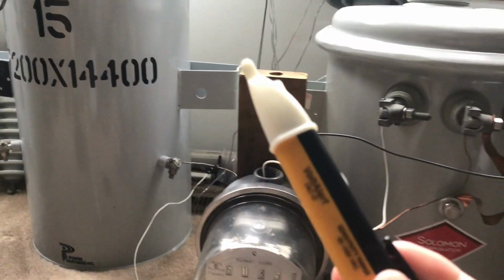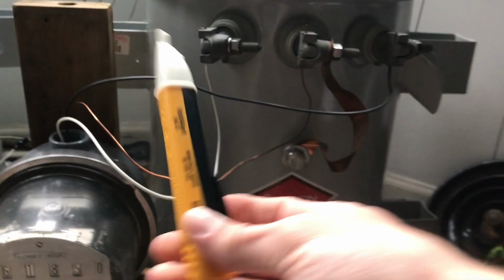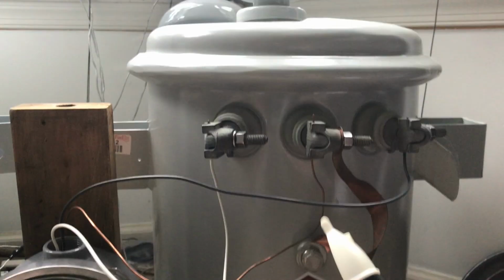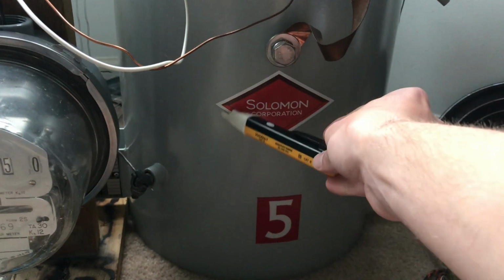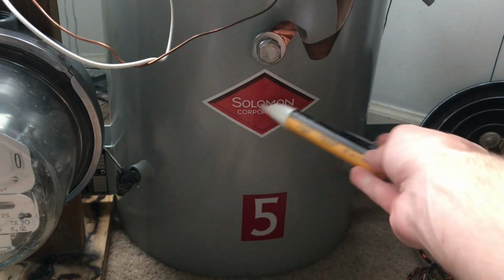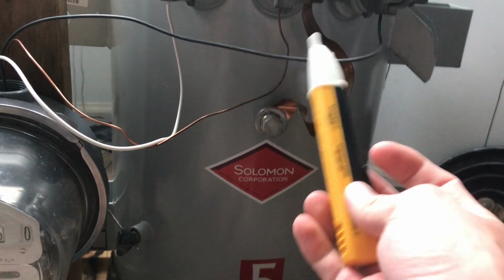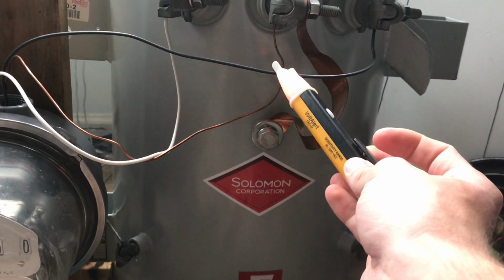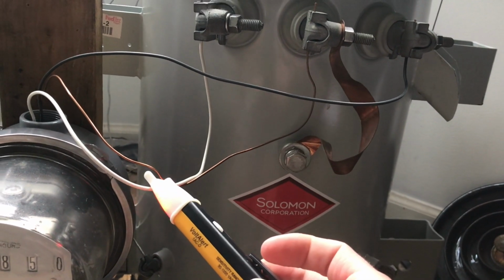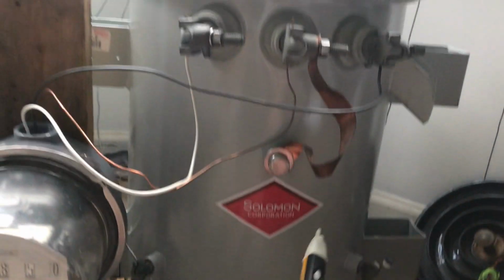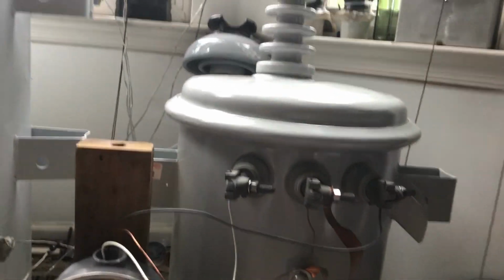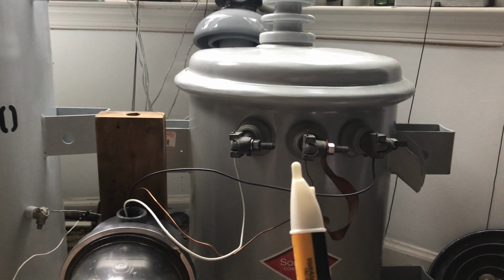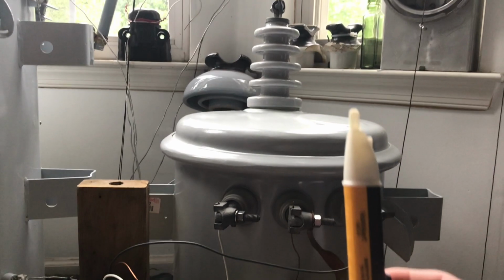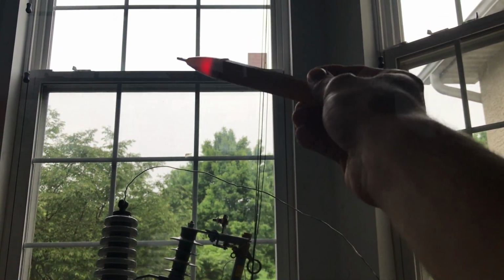And while I still have this going, just a neat little trick with a non-contact pen tester. As you can see, the ground is the ambient voltage. You know, it's not going to pick up the ground, but it'll pick up hot wire, another hot wire. But with 7200 volts inside, once you get above that shielded area, it's out in the open, you know. Just thought I'd show you that little trick.